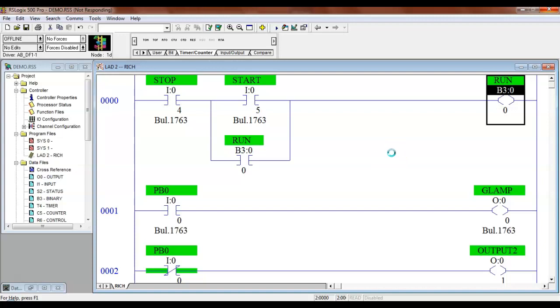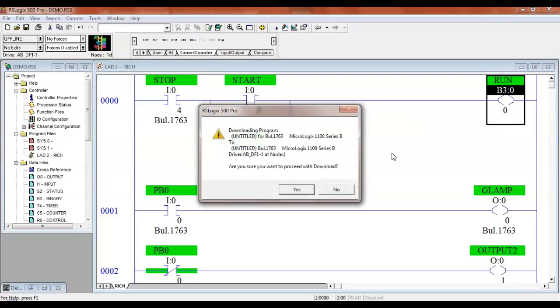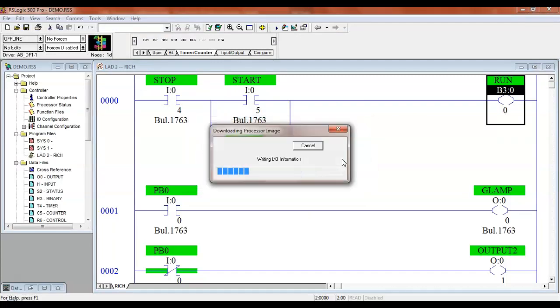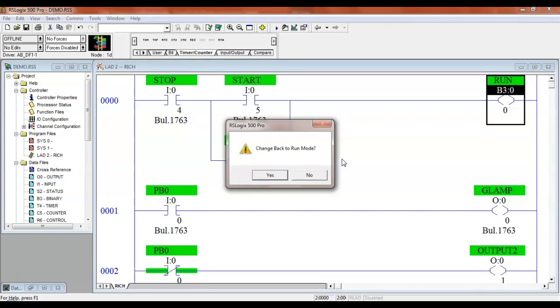By the way, normally when we call a PLC, we talk about what powers it. And then after that, we talk about how we power the inputs. And then the third thing we do is how we power the outputs. So I would refer to this as an AC, because we power it up on the AC. So you see this power cord coming in on the bottom. Then we'd say DC. So this guy here runs DC inputs. And then we would say this guy here runs relay outputs.